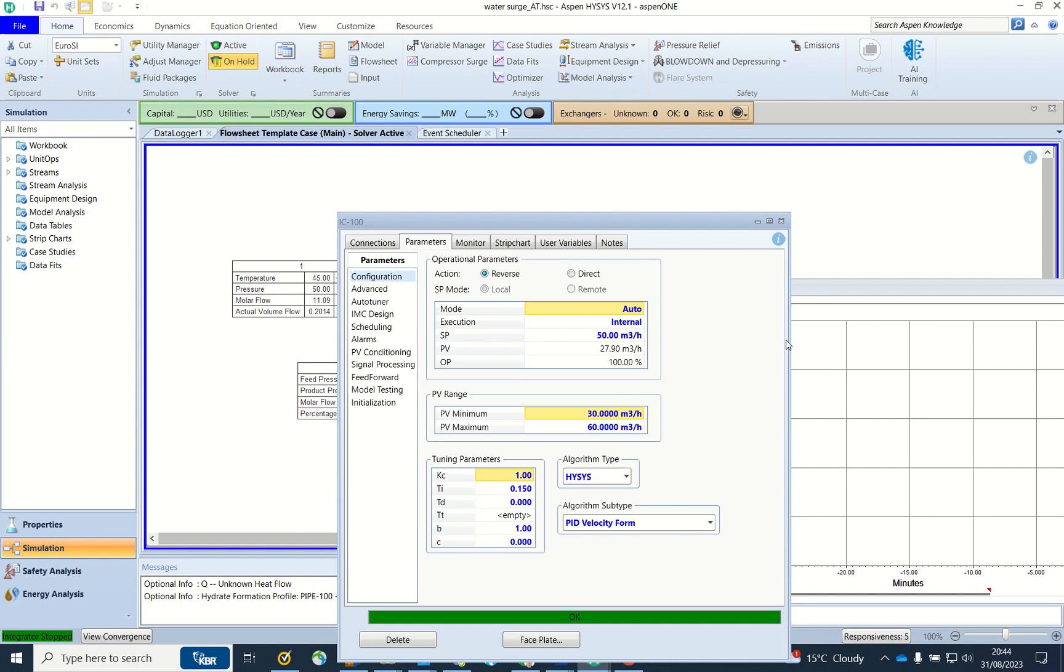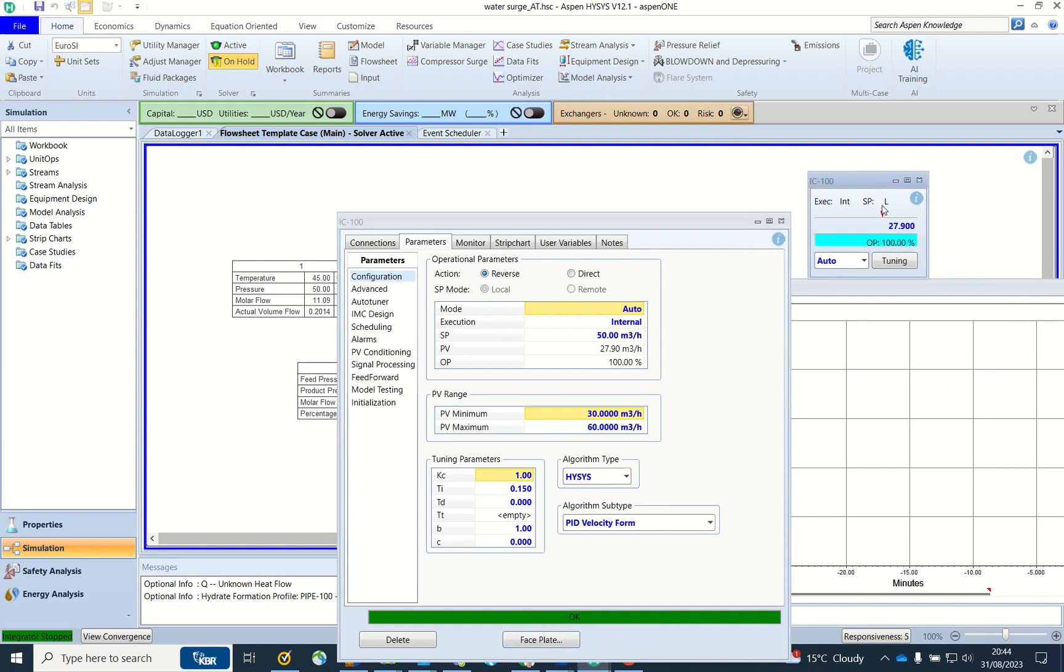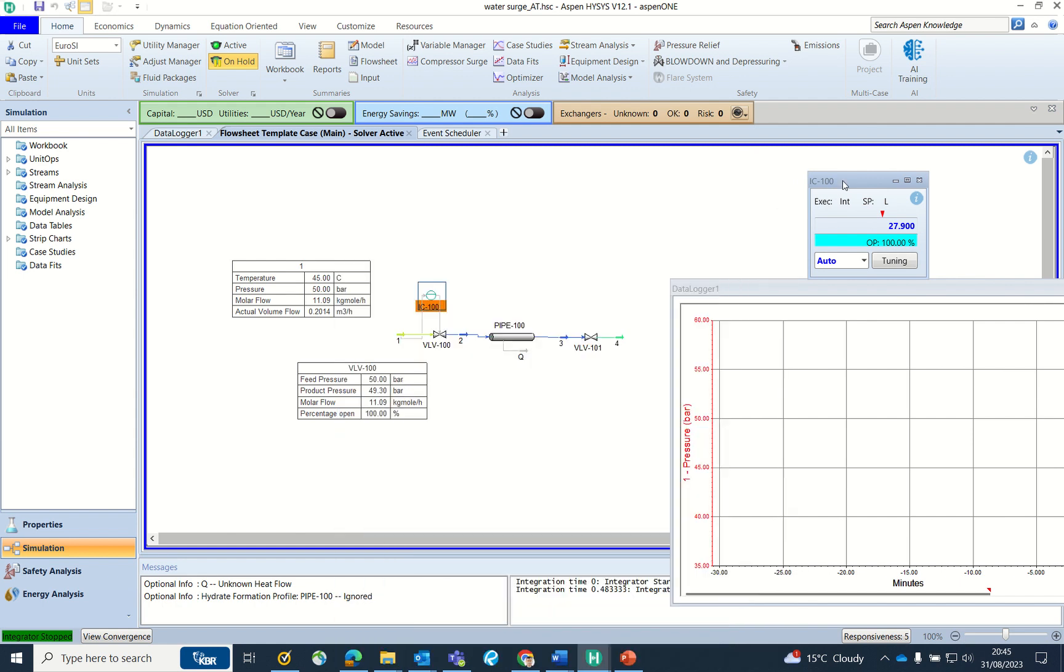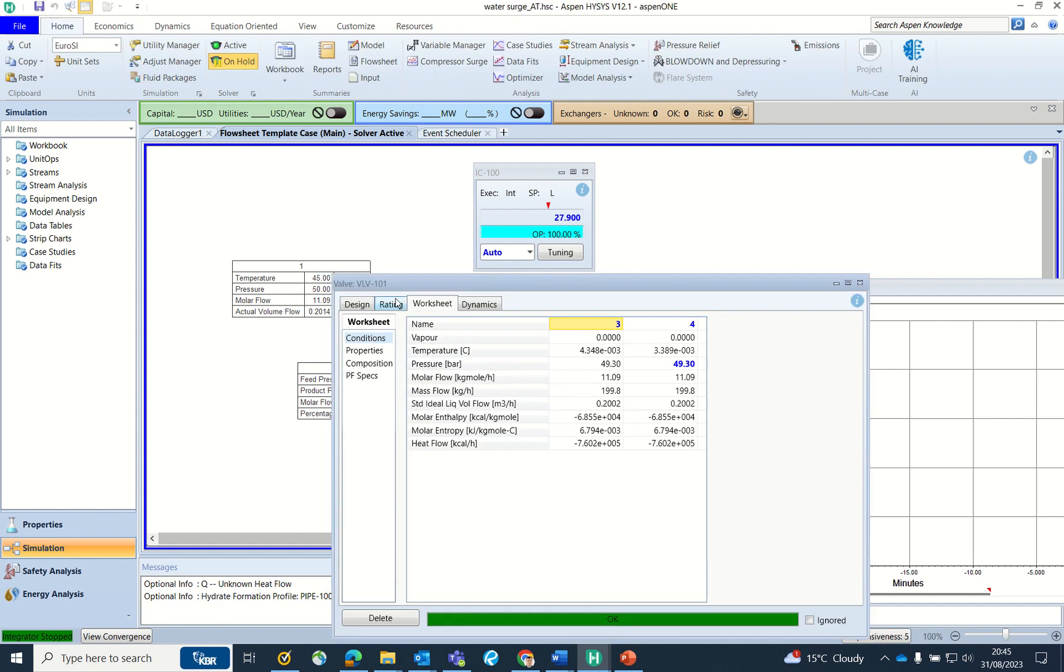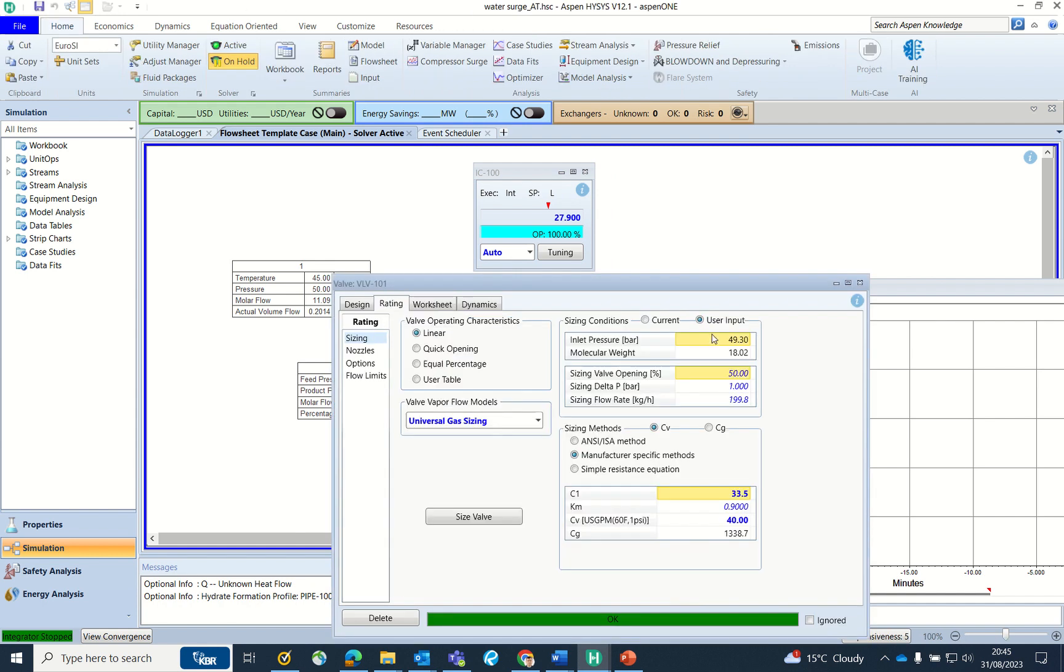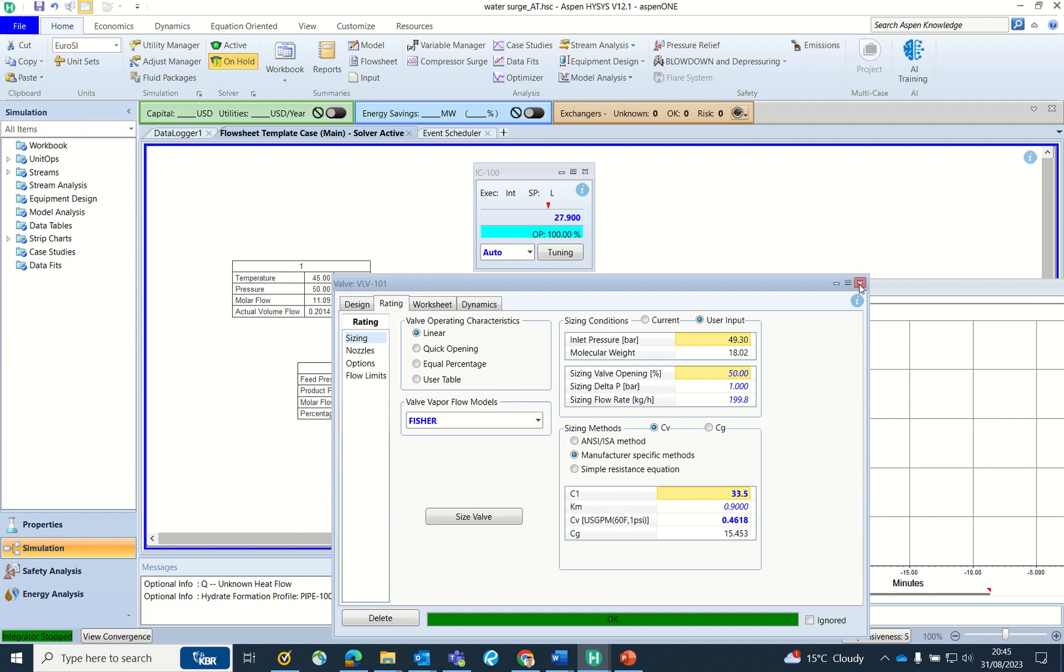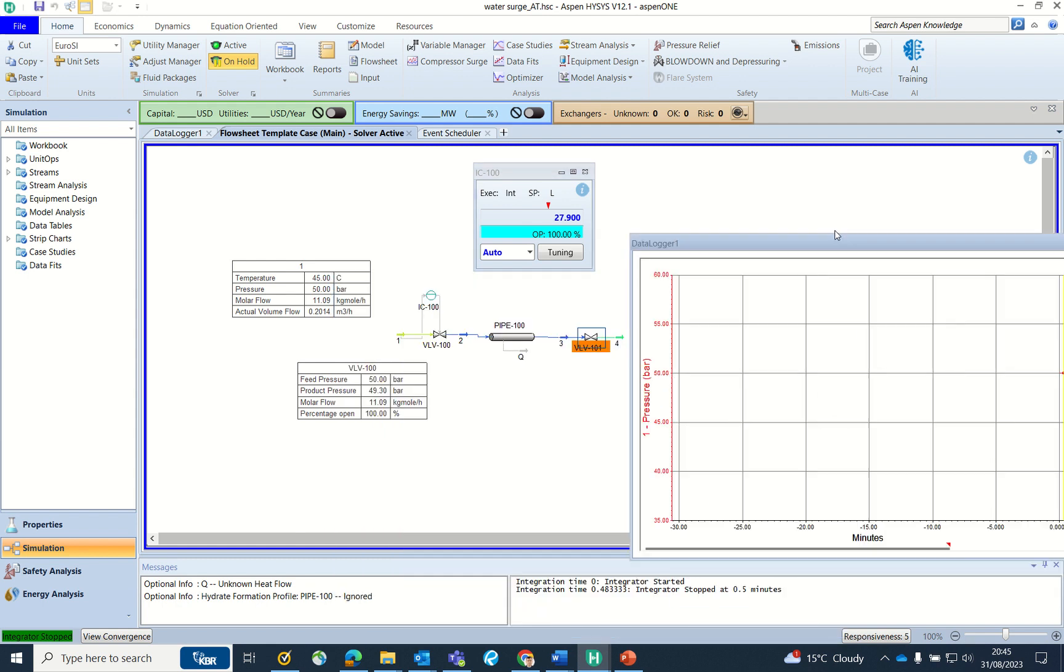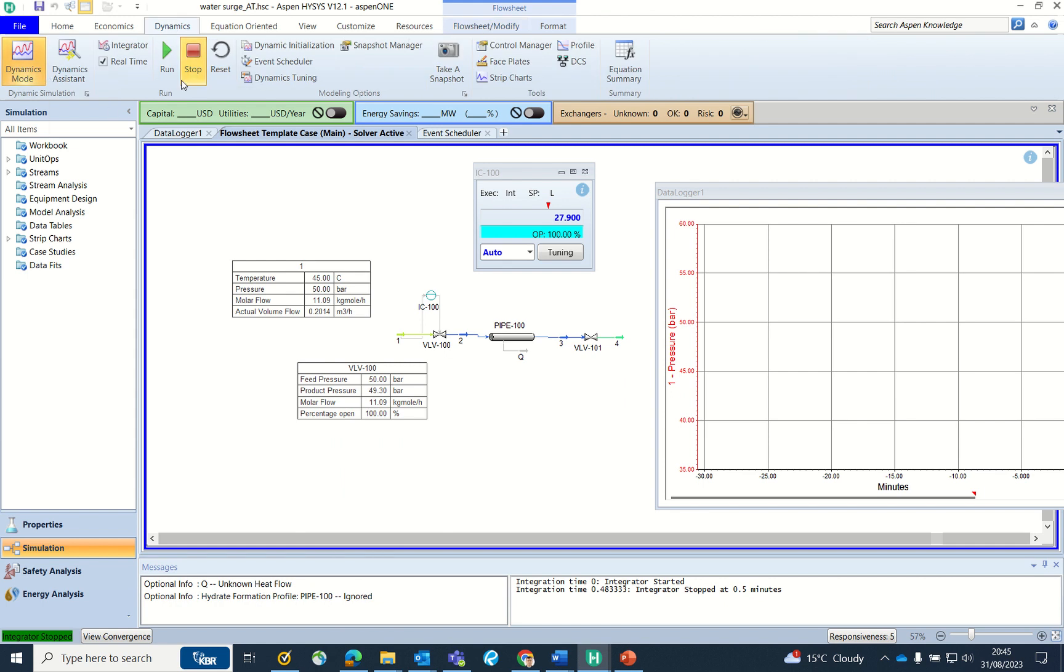The Kc and Ti values have been inserted based on the flow rate of the liquid line, and it is reverse acting as you can see. I can show you the faceplate as well which shows the auto conditions and the manipulating conditions for this control valve. The second valve I have also sized based on HYSYS sizing, and you can see the CV value and percentage opening.